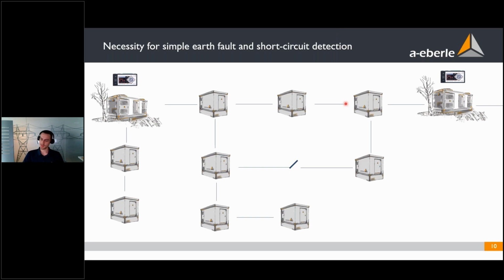Here you see a simplified grid with two digital substations or two intelligent substations that both have an EOR-3DS or multiple EOR-3DS inside them. And in between these bigger substations, there are your simple or non-intelligent substations. And then when a fault occurs, both of your digital substations or the EOR-3DS inside of them will point into the fault direction. But as you see here, this information is not sufficient to precisely locate the fault. You only see that it would be in this area or this section.